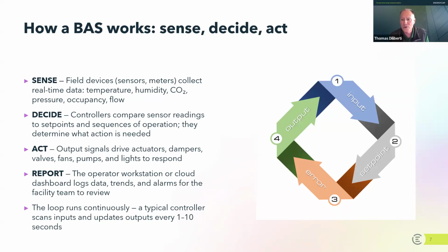So the third thing the system will do is check for errors. You have to identify a range of how far away from the set point you'll accept before you're, quote unquote, in error. And then the system has to adjust. So the fourth thing it does is create an output. Logically, the sequence is this: it takes an input, compares it to a set point. If it's an error, then the system will say, well, let's change the output. Let's change the flow of air, or let's change the temperature. Let's do something within the building in order to bring us back so that we have no errors, so that we're within range. The other thing that happens with these systems is they run continuously.